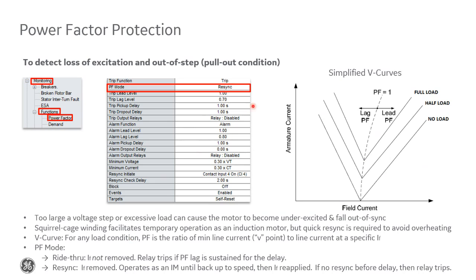On the other hand, if this PF mode we select to be resync, then we'll immediately remove the field and we will shed the load. We'll let the motor run in induction mode to try and resync. Then upon resync, we'll reapply the field and the load. Again, if there's no resync seen before this time delay expires, then we'll trip the motor offline.